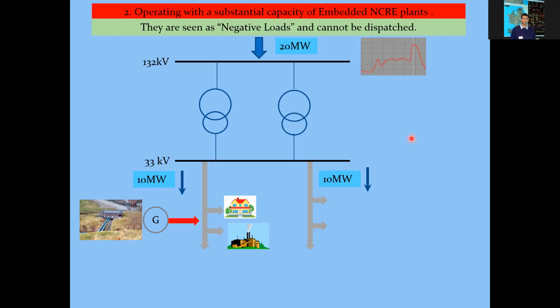During off-peak, it would not be a problem at all because during off-peak, we have a lot of excess generation. Even during off-peak, let's say by 2 a.m., 3 a.m. in the morning, the demand would be about 1,300 megawatts. But the problem is we have too much generation, right? As a result, for example, our coal plants, each coal unit of 300 megawatts will be deloaded to its minimum stable load, which is 180 megawatts. So during off-peak at about 2 a.m., our coal plants would each be running at 180 megawatts. So that is 540. Then when we add all other power stations, there is enough spinning reserve. There is enough reserve capacity to be taken up in case of an increasing demand.